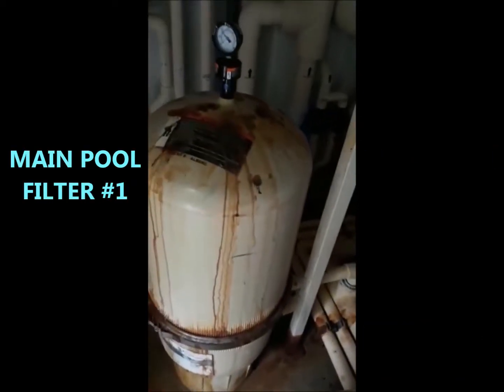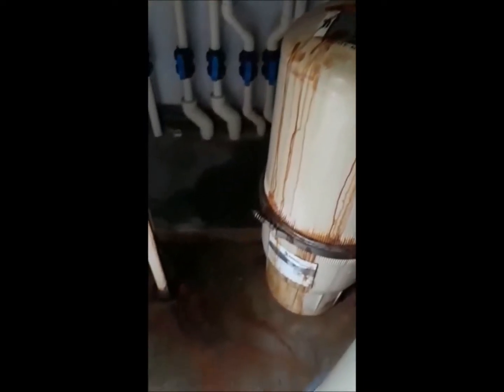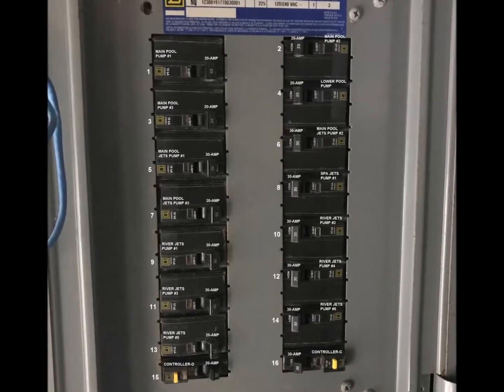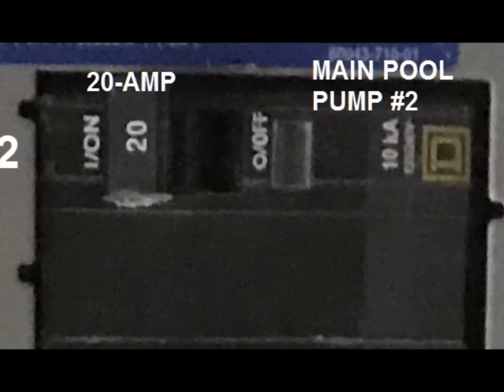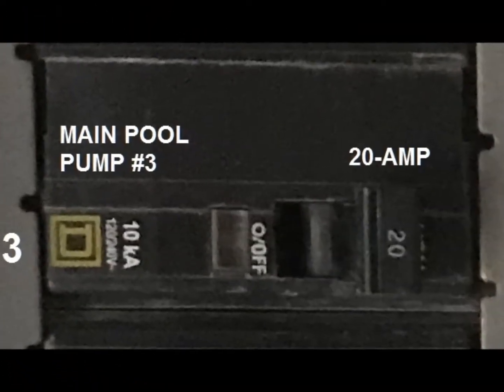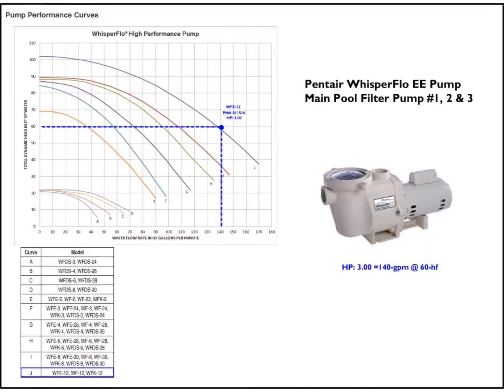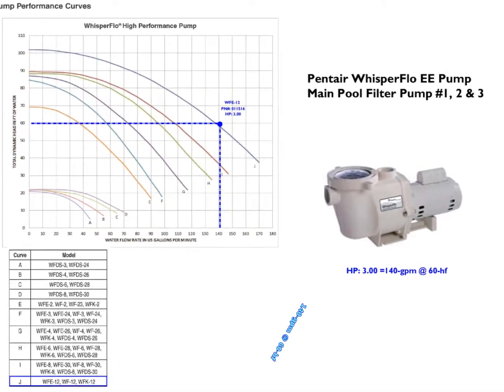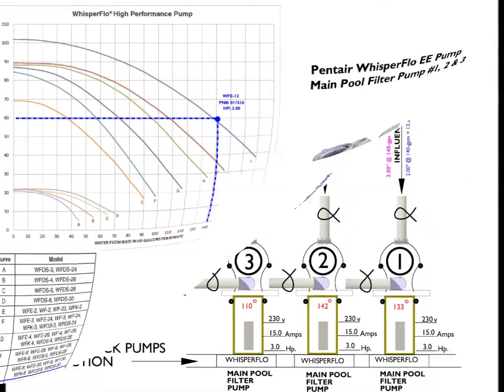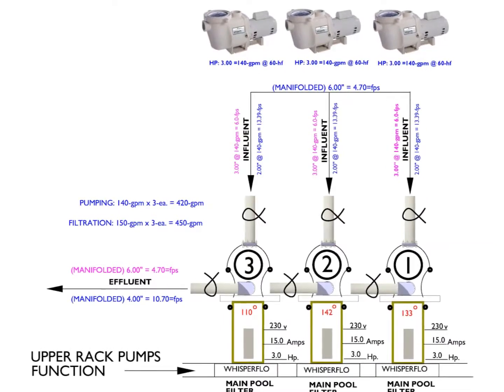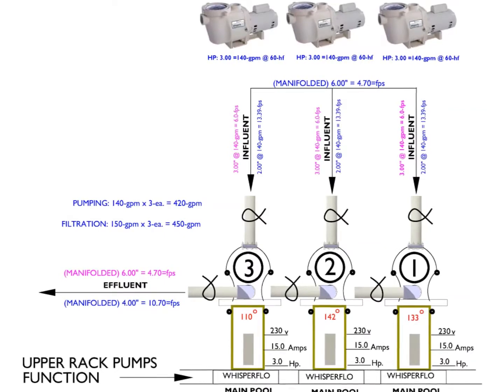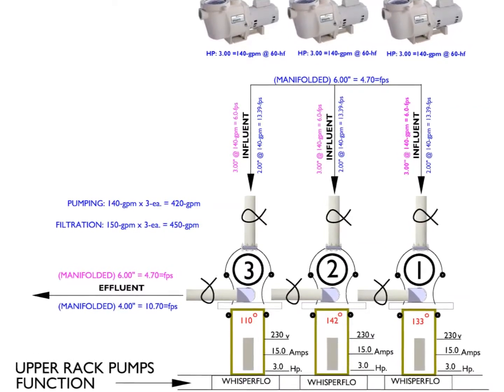Here are the other two main pool filters 1 and 2 previously mentioned. Power to each pump is distributed by individual circuit breakers, numerically labeled accordingly to each pump and rated for each pump's amp load. These are located inside subpanel A together with the circuit breakers for the automation controllers. The main pool has three dedicated WhisperFlo 3 horsepower pumps capable of delivering 140 gallons per minute at 60 head feet, manifolded together with a 6-inch influent suction supply and a 4-inch effluent return discharge.